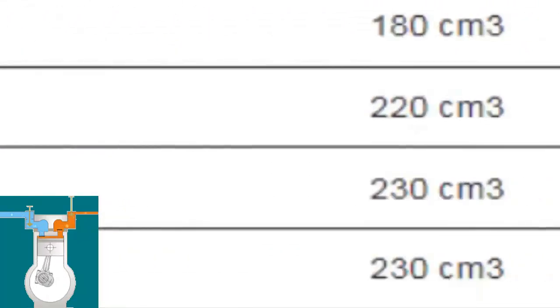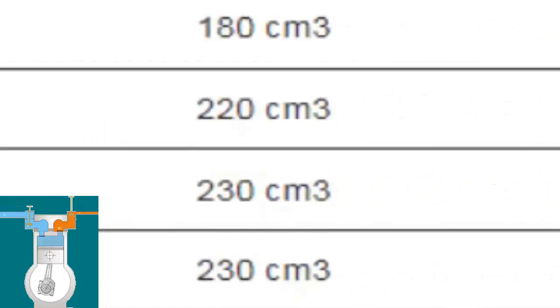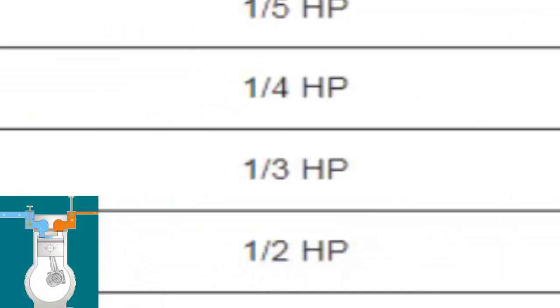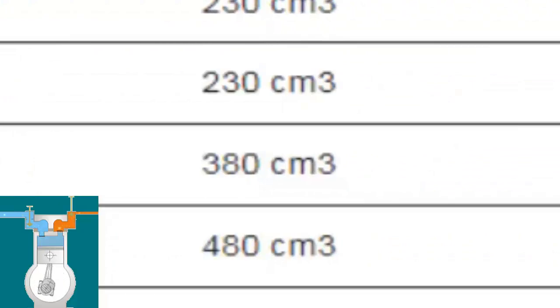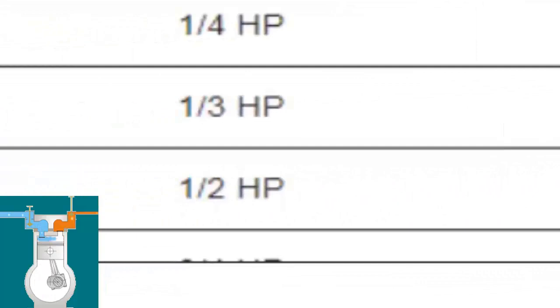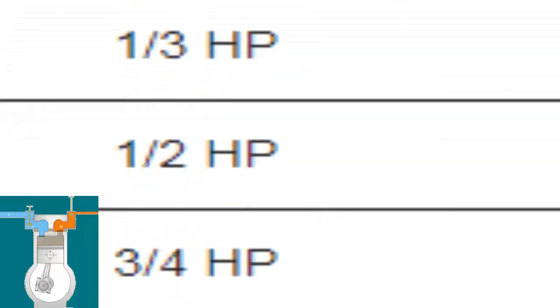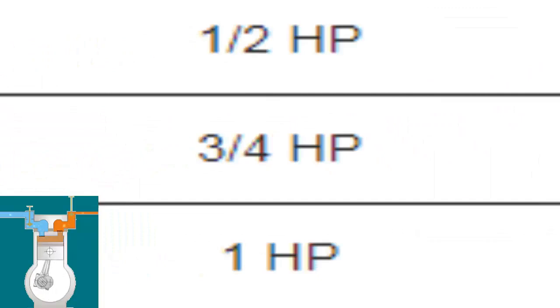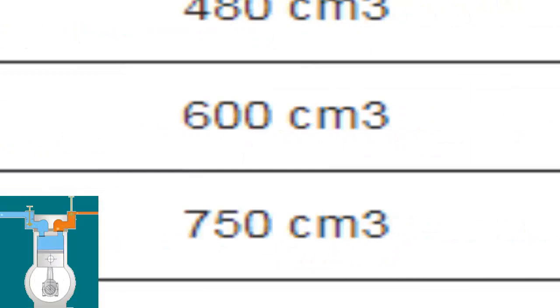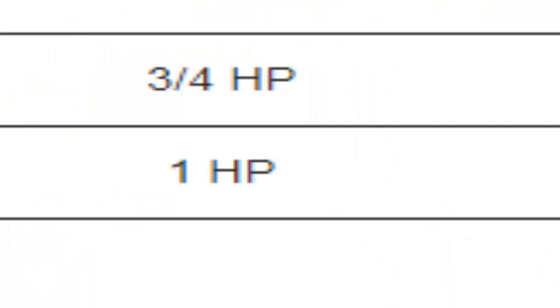1/5 HP compressor with an approximate oil quantity of 230 cubic centimeters. 1/4 HP compressor with an approximate oil quantity of 230 cubic centimeters. 1/3 HP compressor with an approximate oil quantity of 380 cubic centimeters. 1/2 HP compressor with an approximate oil quantity of 480 cubic centimeters. 3/4 HP compressor with an approximate oil quantity of 600 cubic centimeters. 1 HP compressor with an approximate oil quantity of 750 cubic centimeters.